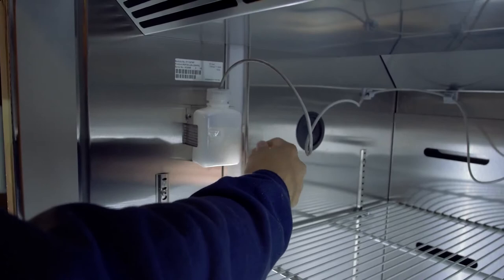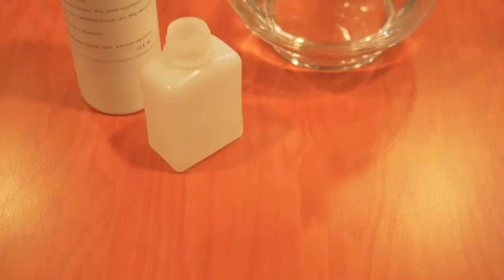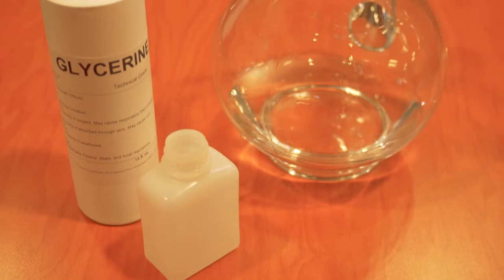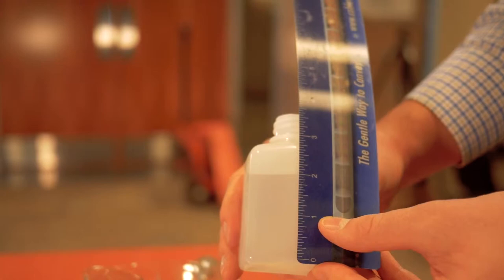Open the door to locate and remove the product simulation bottle from the side wall of the storage cabinet in the refrigerator. Using the provided glycerin solution in the cardboard accessory box, fill the bottle with the appropriate amount of glycerin and water. Use a ruler to measure the distance in inches from the bottom of the bottle to the base of the bottleneck.